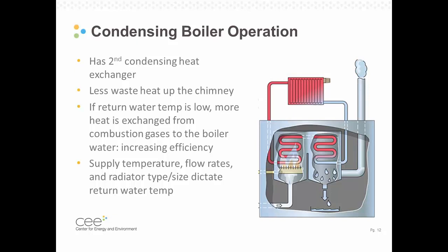So again, the more heat that's extracted out of the gases, the less that goes up the chimney. And that is what helps increase the efficiency. You can't typically set the return water rate. You're typically setting the supply water rate, and so that supply water temperature set point as well as your emitter capacity is what really dictates that return water temperature.